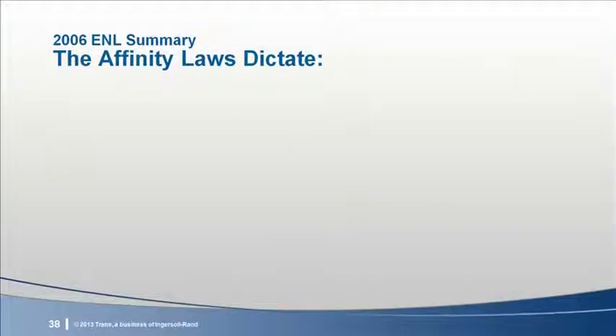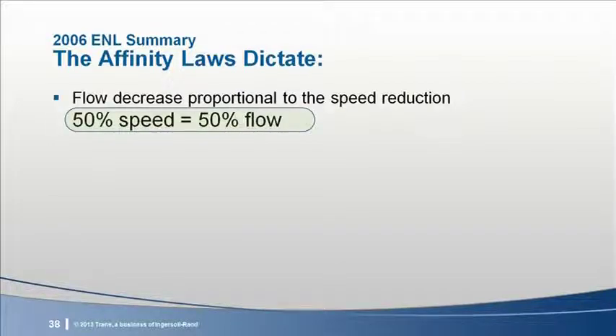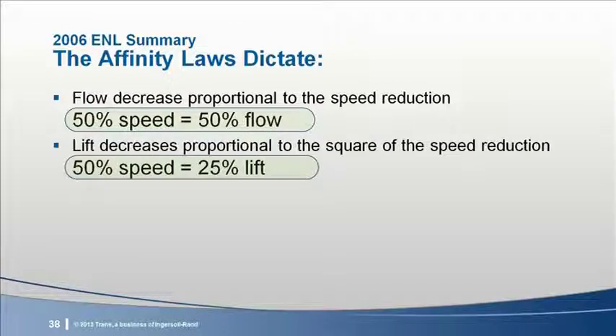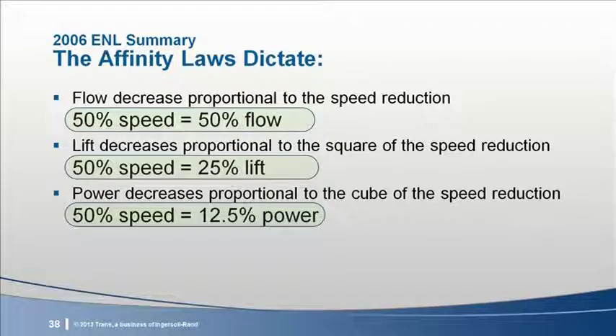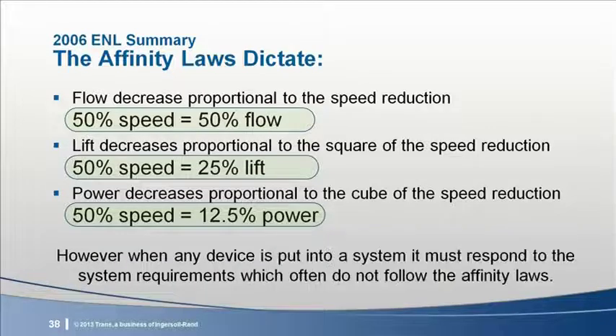Let's see what we discovered in the previous Engineers Newsletter. The performance of dynamic variable speed devices such as centrifugal fan wheels or pump and compressor impellers follows the affinity laws, which state, as the speed is reduced, the flow through the device decreases proportionally. The available pressure rise from the device, also known as lift, decreases proportional to the square of the speed reduction, and the power use then decreases proportionally to the cube of the speed reduction. These principles apply only to the fan wheel or impeller operating by itself. In reality, a variable speed device is almost always part of a bigger system, and the operating characteristics of that application will dictate how the device performs. Let's look at a few applications and see how this plays out.